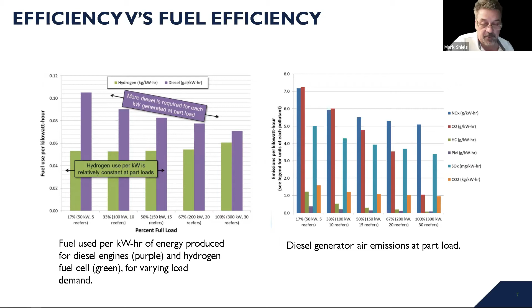Part load behavior of diesel generators also has an adverse effect on air emissions. The figure on the right shows air emissions for the same diesel generators operated at part load, and in all cases, the air emission per kilowatt hour of energy produced becomes worse as the load is reduced, which is kind of counterintuitive. This report, by the way, is provided by Sandia, published in 2017, but it's still pretty relevant today.